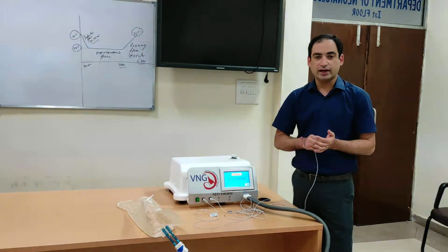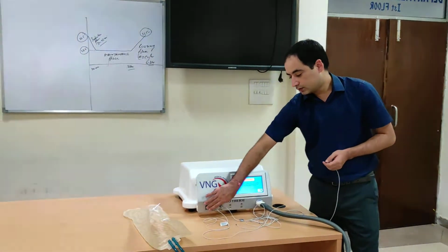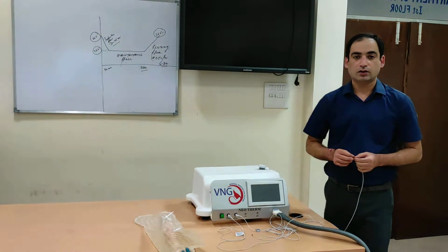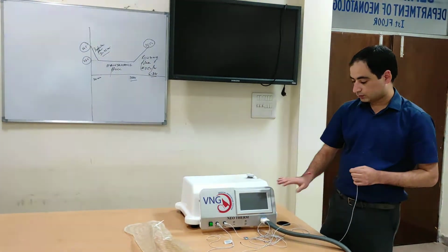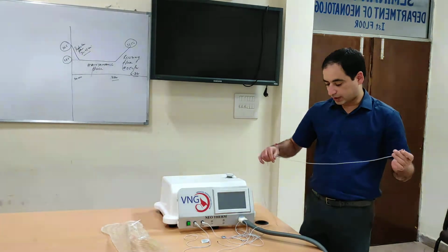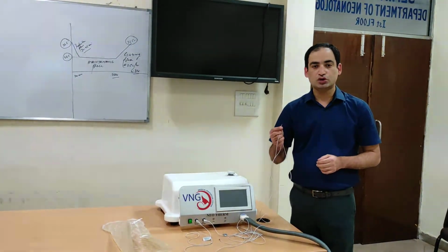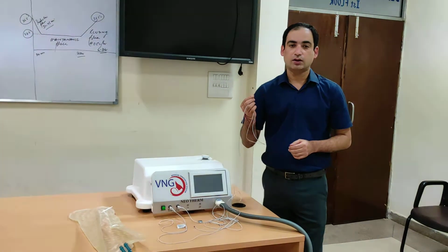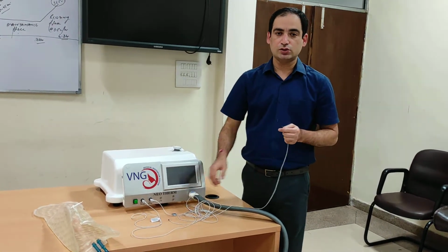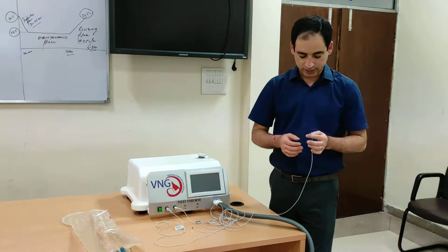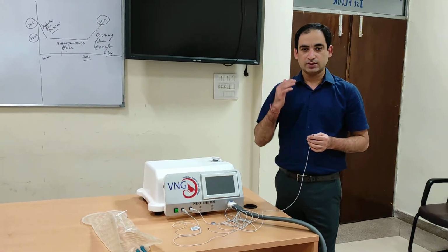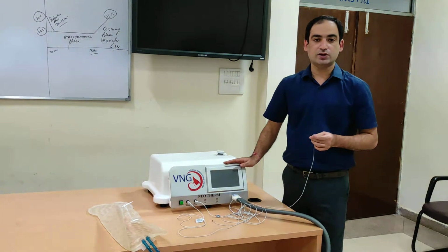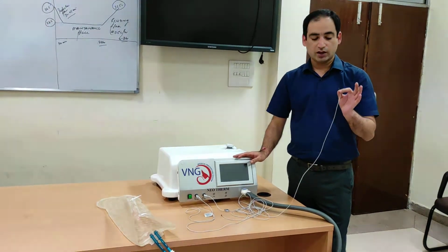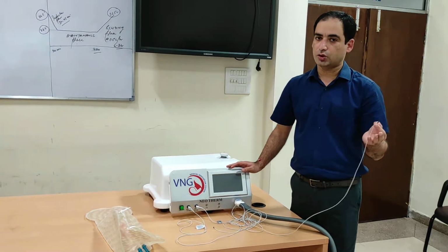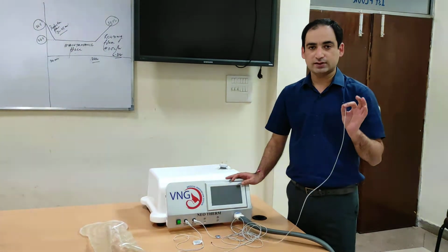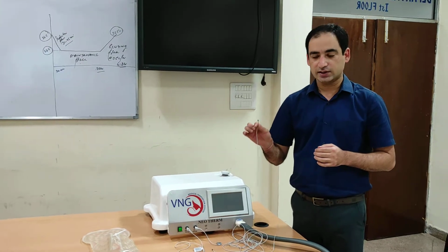If you do not attend to this alarm, the machine will go back to a standstill mode. So that shows that whenever there is an alarm, the most common cause is displacement of the rectal probe. Whenever the baby passes the stool or shivers or makes some movements, the rectal probe can get displaced. So always the first step, whenever there is alarm and the temperature is out of range, look for the rectal probe. If it is displaced because of the stool, which is the most common cause, clean the stools and put back this rectal temperature probe 3 to 5 centimeters inside the rectum.